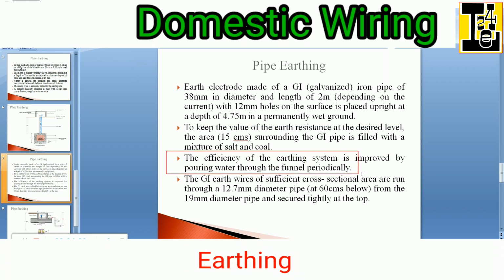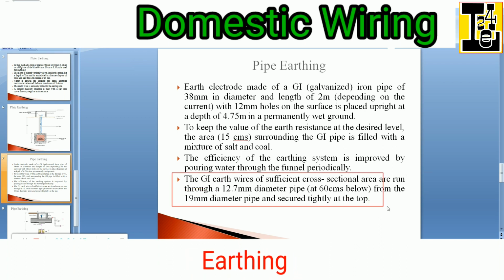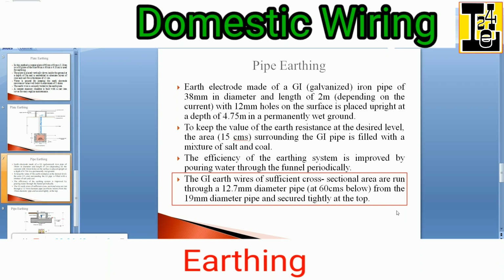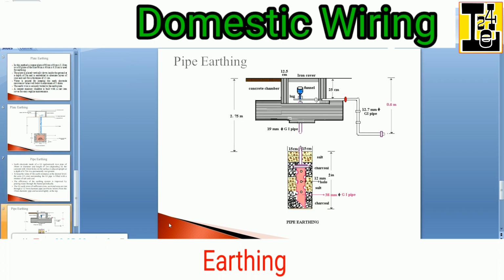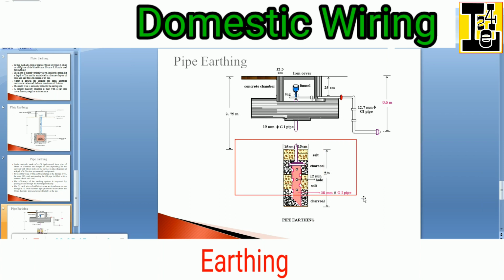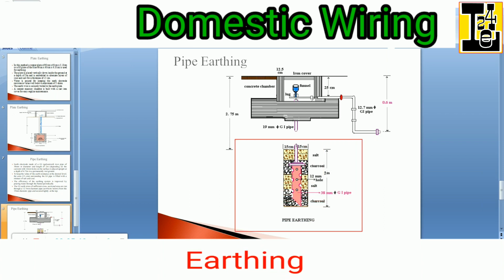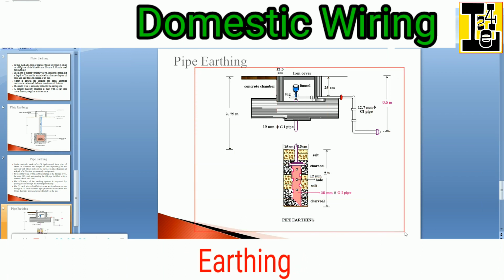The efficiency of the earthing system is improved by pouring water through the funnel periodically. You might have observed that we need to pour water at the earthing place through the funnel which is provided. The GI earth wires of sufficient cross-sectional area are run through a 12.7 mm diameter pipe at 60 cms below from the 19 mm diameter pipe and secured tightly at the top. You can observe the pipe earthing arrangement over here. This is how the pipe is buried inside the ground. So this is the entire arrangement for the pipe earthing.